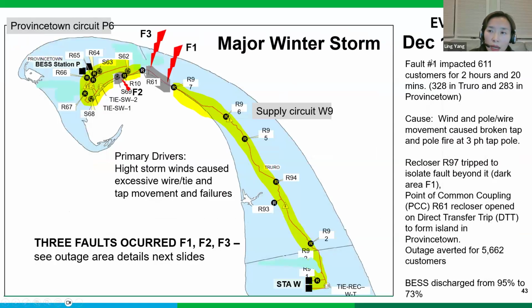This is another application where the battery was kicked in to support during a major winter storm last December. The first fault happened between this recloser and this recloser. So the battery quickly formed an island at the point of interconnection. And the unfaulted circuits, like south of the circuits, were picked up by the source station, and the fault was isolated, and the battery was able to pick up all the customers down in Provincetown.